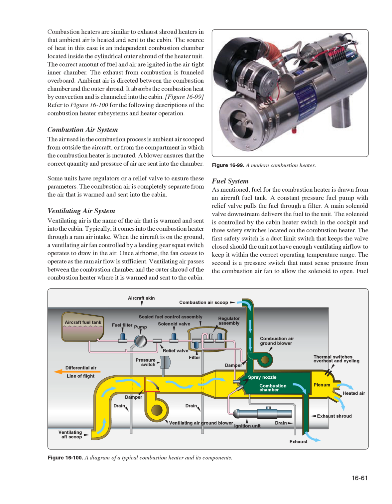Ventilating air passes between the combustion chamber and the outer shroud of the combustion heater where it is warmed and sent to the cabin. Fuel system. As mentioned, fuel for the combustion heater is drawn from an aircraft fuel tank. A constant pressure fuel pump with relief valve pulls the fuel through a filter. A main solenoid valve downstream delivers the fuel to the unit.